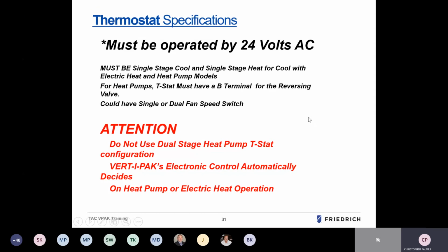The thermostat connections are 24 volts and must be operated with a 24 volt thermostat. These are standard 24 volt units. They do not operate under any kind of DC voltage or any kind of multi-phase voltages or anything like that. Must be single stage cooling or single stage heat for cool with electric heat pump models, and the heat pumps must have a terminal B, which controls the reversing valve connection. You can have the option of a single or dual fan speed switch, but do not use a dual stage heat pump thermostat. The Vert-I-Pak's electronic control automatically decides heat pump operation or electric heat operation.